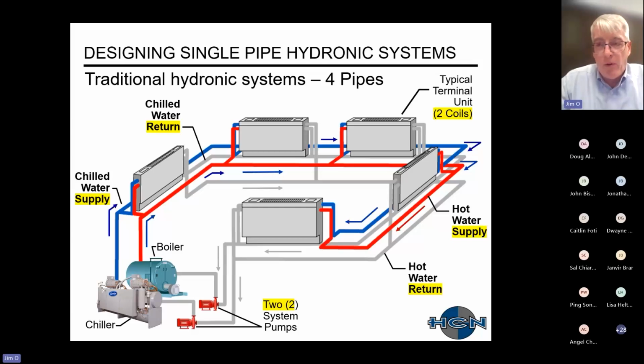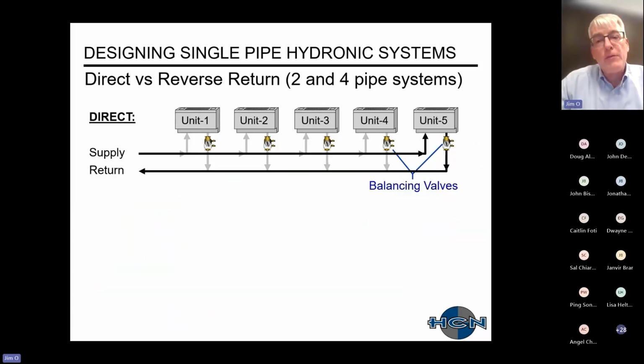And just want to point out that inside the terminal units, you now have two coils. They're two separate coils. They don't cross over like they do in a one-pipe system. And then also now you have two independent system pumps. Just to go through some more basic information about piping systems.